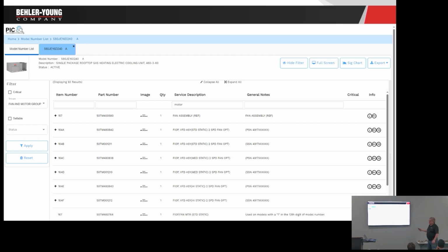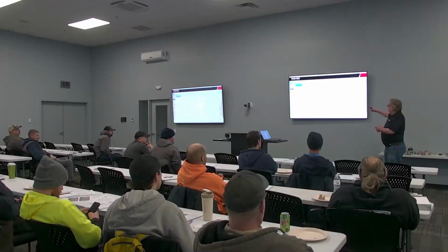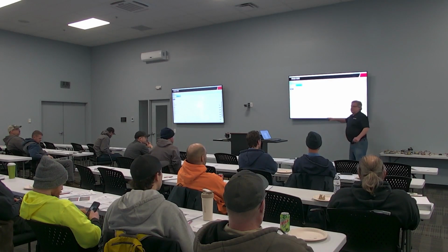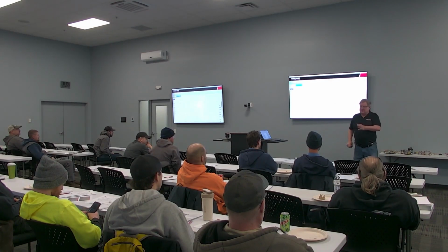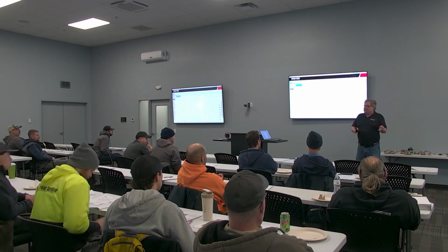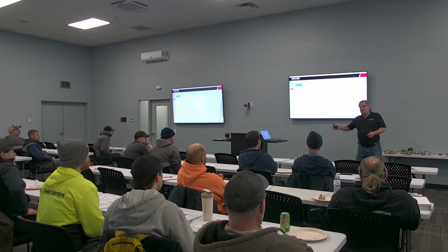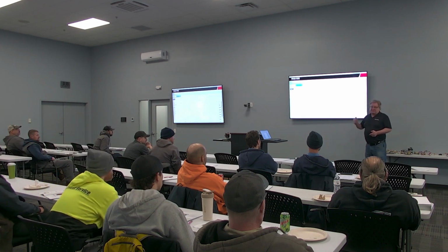We do need that whole number, because we do get a lot. That happens not a ton, but it does happen. We're getting a call: well, this blower keeps kicking out. As we start doing some research, you got the wrong blower motor. The blower motor for the VFD is not the same blower motor for that same unit without the VFD, the one with the overload on it. So if you get a 2016 rooftop unit that didn't have VFD on it, the blower motor is different than the 2017 that did have the VFD. The blower motor for the VFD does not have an overload. The one without it does, and that overload will cause the VFD to trip out.